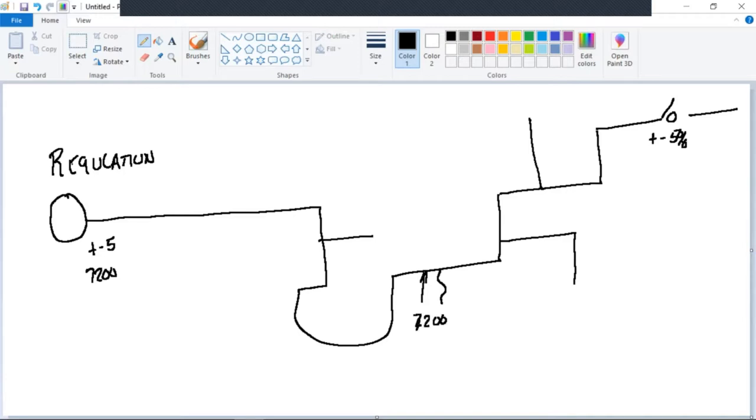Okay. I also don't want to be over 5% at the beginning. Voltage drops as you go down the entire circuit because one, of impedance, and two, load that's on the circuit. I also, at the end of my circuit, don't want to be below what? 5%. The minus 5% on my circuit. So that's why you have voltage regulation that goes up and down. Now, why would you think voltage would change on a circuit just through the course of one day?